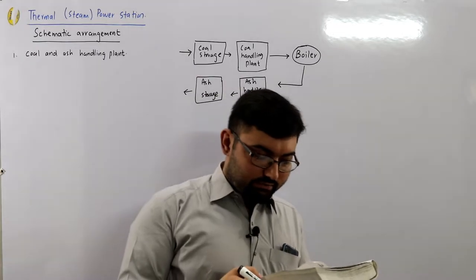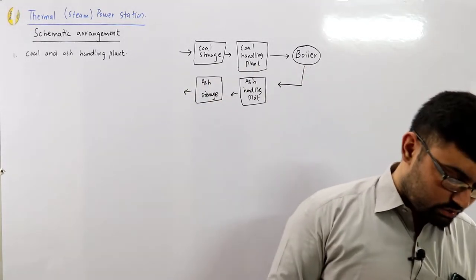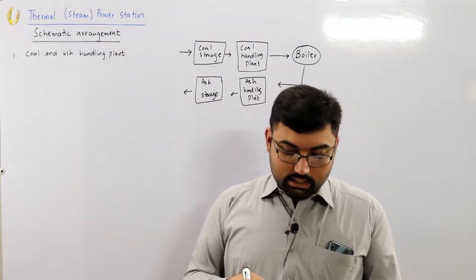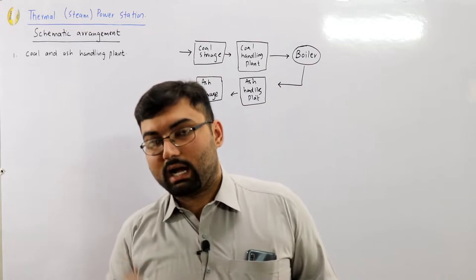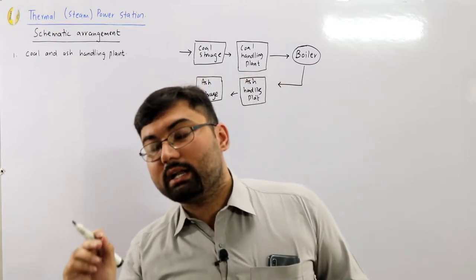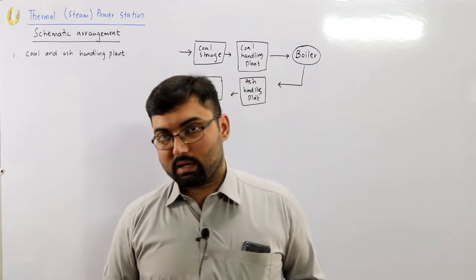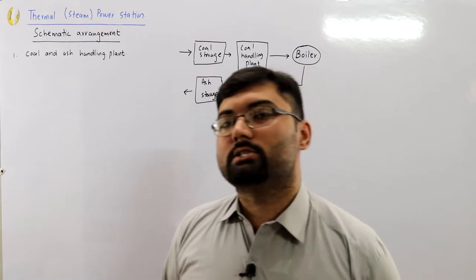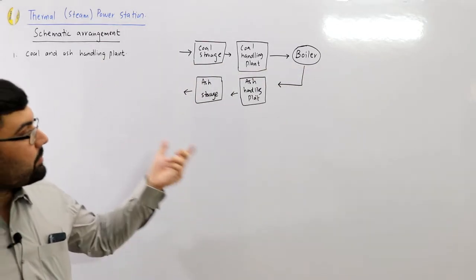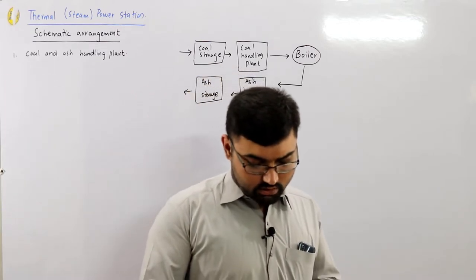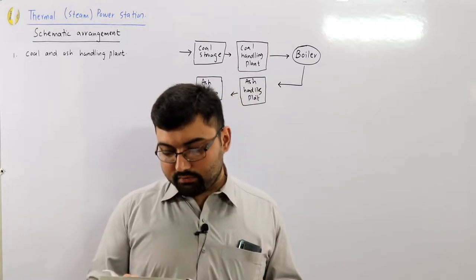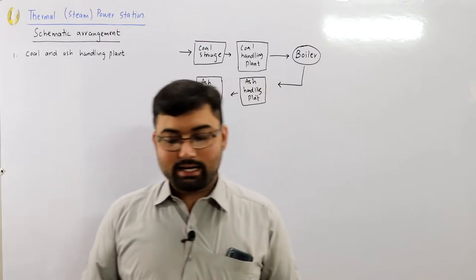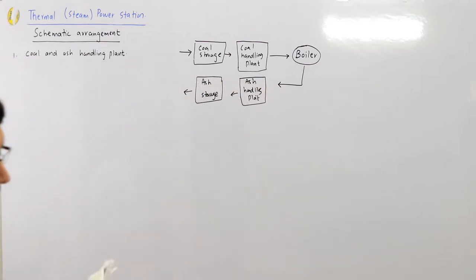It is worthwhile to note the amount of coal required: a 100 megawatt station operating at a 50% load factor requires about 20,000 tons of coal per month. Ash is about 10–15% of that, so roughly 2,000 tons of ash must be removed. In a thermal power station, about 50–60% of the total operating cost consists of fuel purchasing and handling.